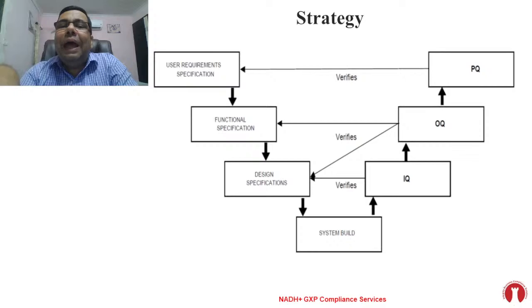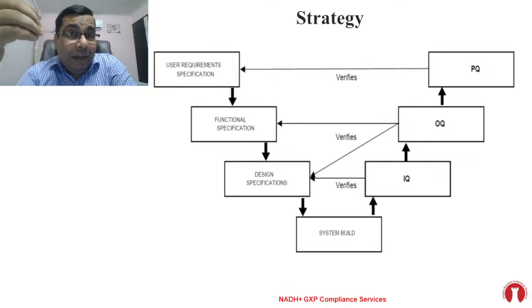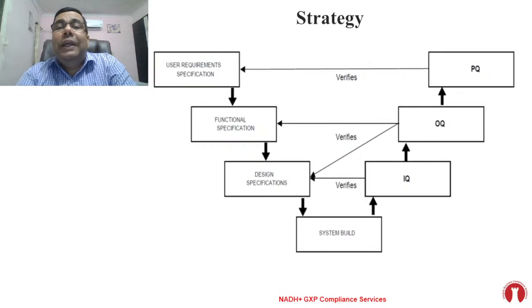When I perform the IQ, I have to ensure that whatever design is made complies with the design, and at the same time complies with the functional specification. So I need to verify my requirements indirectly at each stage. You can see this in the OQ also, and even at the PQ. At the final stage of PQ, you can see the return arrow again to the URS.